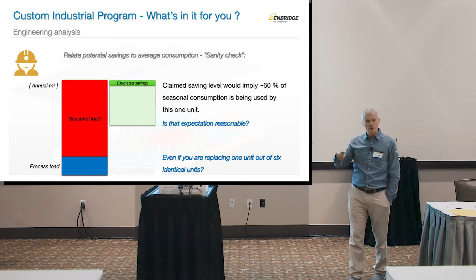So when we saw this, we called the vendor back, and we talked, vendor, customer, myself. What it turned out to be is that they were based on 12% better efficiency, sure. But the assumption was made that the unit operates at the nominal CFM, what's said on the unit itself, year-round, all the time. The problem is, remember that the unit was indirect, and therefore it had recirculation. So only 20% of the air was actually fresh air. Everything else was recirculated. Now the savings and the consumption are much less than what was originally thought. So the customer still went and replaced the unit, but with the knowledge of what's going on. And they actually replaced it with the same indirect one because it allowed them to run only 20% fresh air.